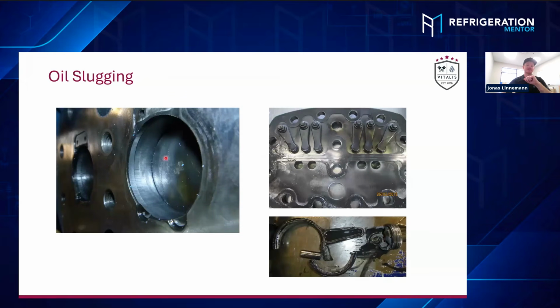So you can see here the piston. Pistons don't really like to compress either liquid or oil. And if you get such a big oil slug back, it just stresses the piston rings, the valve plates will get stressed and break eventually. And the worst case is that you just destroy the whole thing, like the piston rod, the crankshaft, sometimes even the bodies. So there's a lot of force inside these CO₂ compressors, and it's not dangerous as long as you don't get super huge oil slugs back.